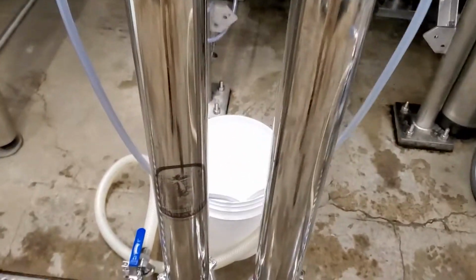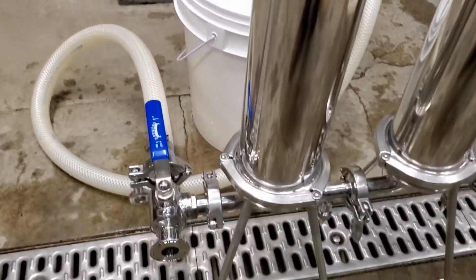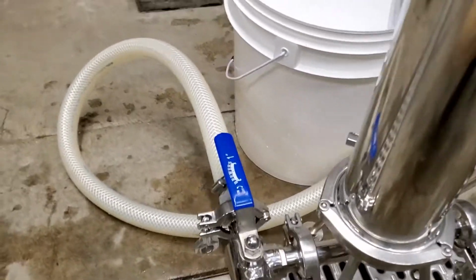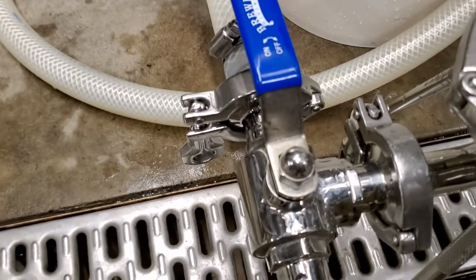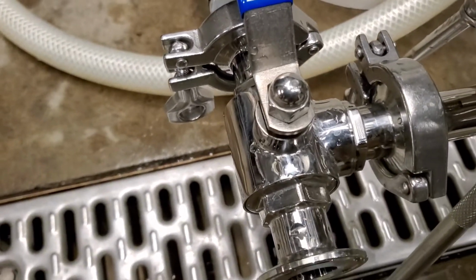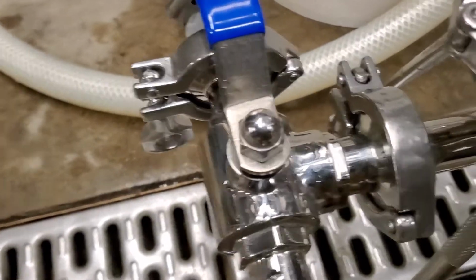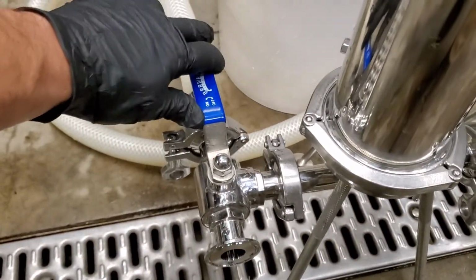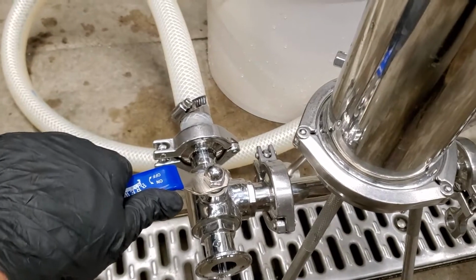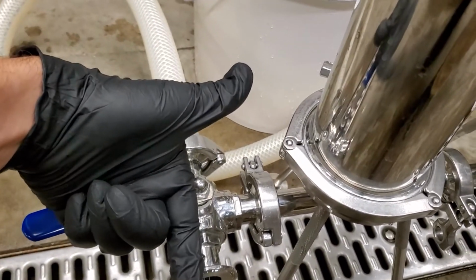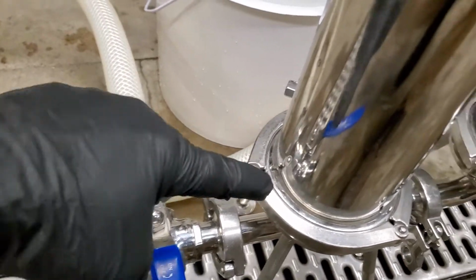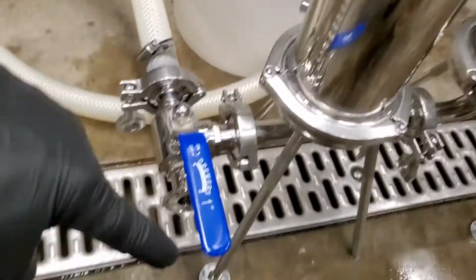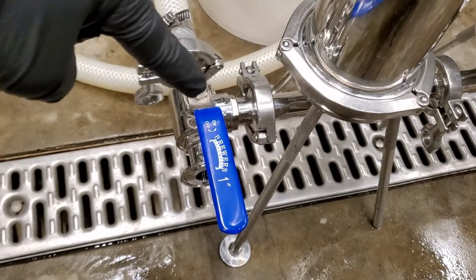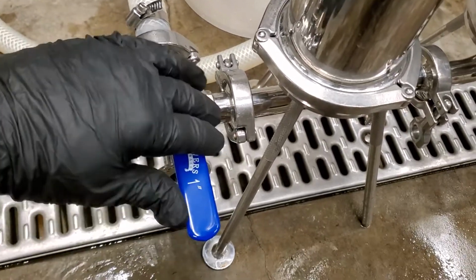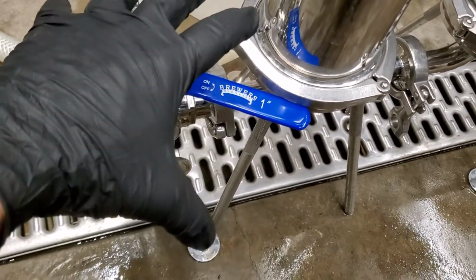Now let's step over here. We're going to make sure our outlet valve is in the correct orientation, and it should be here. This is a T valve. If you have this full port T in this position, it just goes straight through as a T. If you have it in this position, the product will come out and go this direction. If you point it towards the unit, which we can't even do, that's all open.